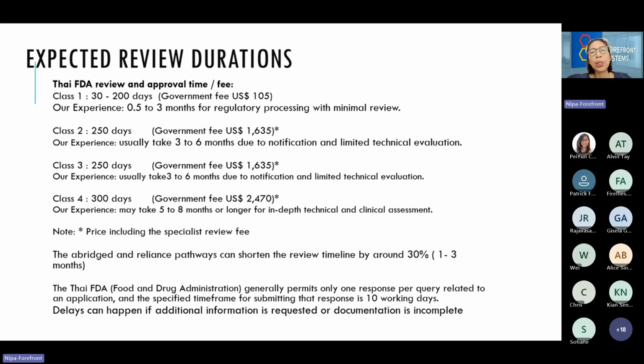So class 1 is between 30 to 200 days. You may question why the range is so long. Some normal devices, for example non-sterile devices, get reviewed and approved fast, but sterile class 1 devices, reusable products, and measuring products will take longer. The government fee will be about 105. Our experience of success for class 1 is about half a month.